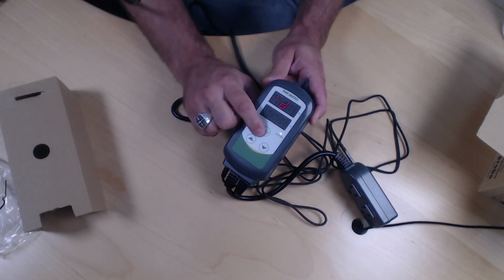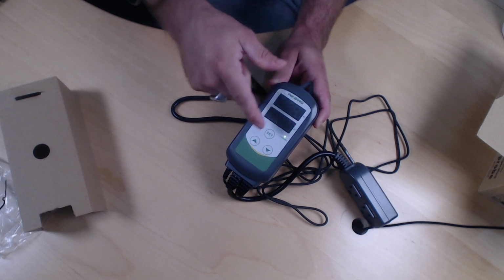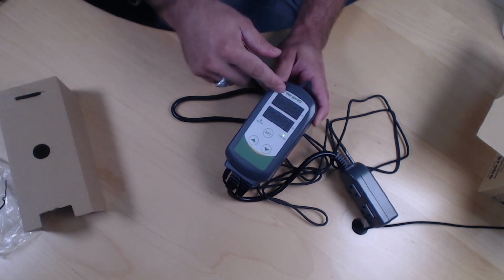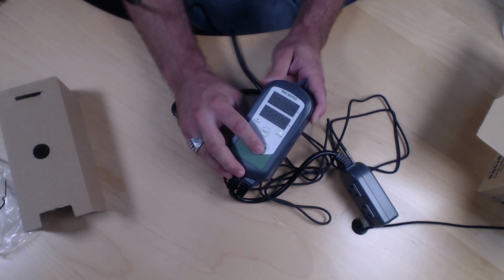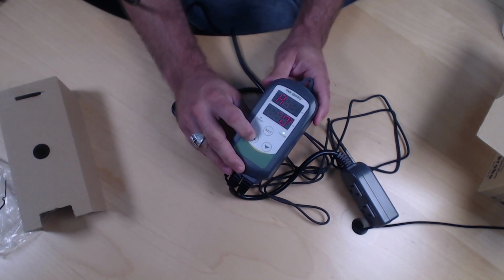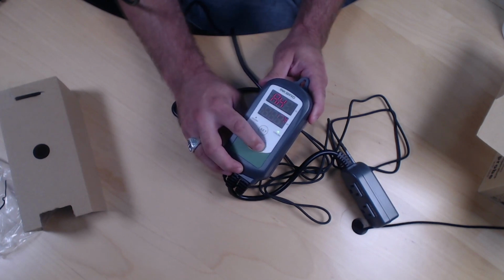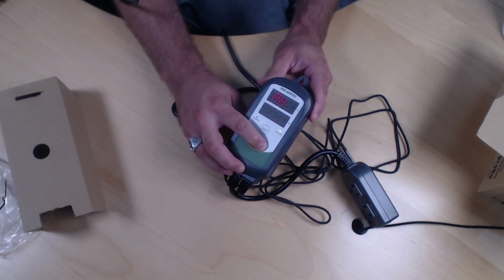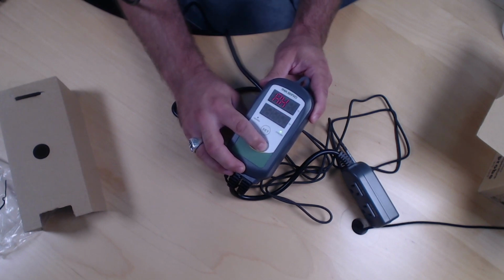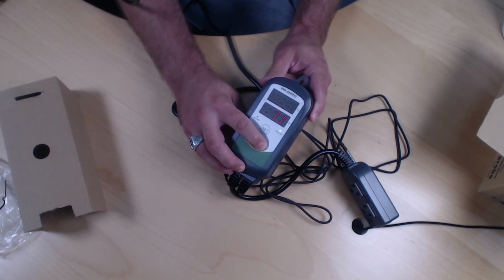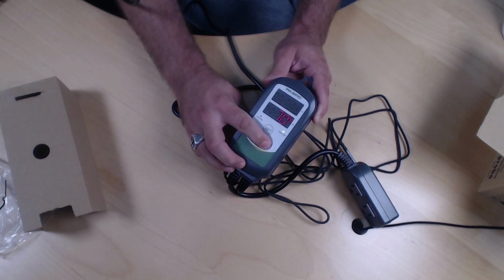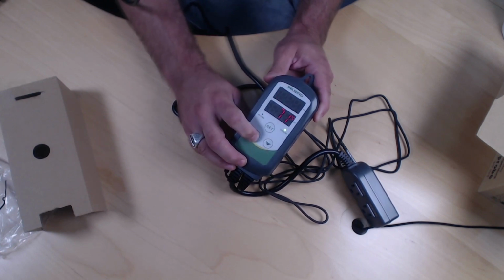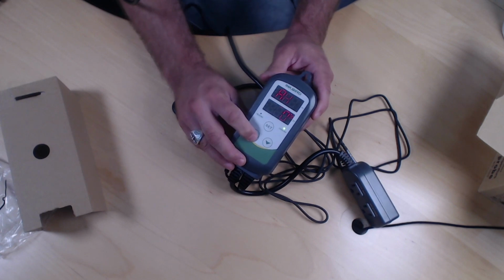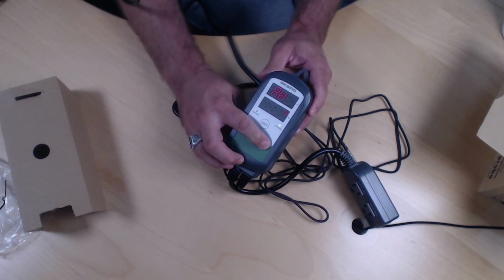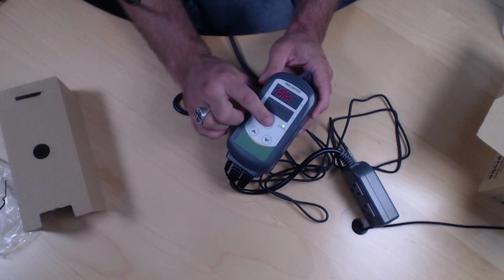Moving on, every time you want to go to the next setting, you just hit set. That locks in the last one. This next setting is AH, which stands for high alarm. This is the setting you'd use when making an alarm to notify you when the actual temperatures reach a certain level. So in our example, if we're using it for ale fermentation and the target temp is at 65, I'm probably going to be worried if my fermentation chamber gets to, let's say, 70. And again, so it doesn't go into operation mode, I'm just going to go back and forth here. Because then when it gets to 70, I can go, crap, my Kolsch is getting a little too hot in there.